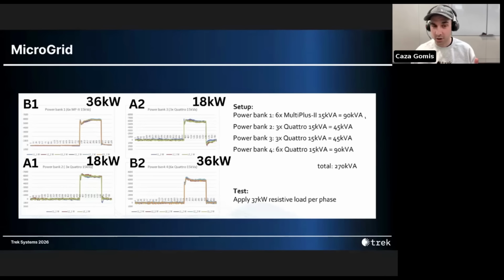And without any additional communications cables between these power banks, they all adjusted their output so that it was proportional, not only across each power bank, but across each inverter within each system. So a quick note that these numbers are rounded. And so if you add up the numbers in our A graphs and B graphs, they're not going to equal 111 kilowatts exactly. But look at how all the lines match up to show that every inverter in this microgrid, all 18 of them, are outputting equally at around 6 kilowatts. And also that power banks B1 and B2, because they are twice the size as A1 and A2, are automatically outputting twice as much power.